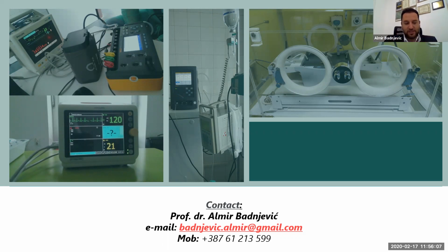For example, a good example is a fridge at your home. When you read the instructions for the fridge, it says you must call authorized distributors every year to clean your cooler or something. I don't know what is written there, but I'm sure that 99% of you are not calling anyone to check your cooler on the fridge until it's broken, until it's not working. In a healthcare institution, they wrote it, but from another point of view, when we are talking about inspection, it's low. So the law of each country is always above any recommendation of the manufacturer.